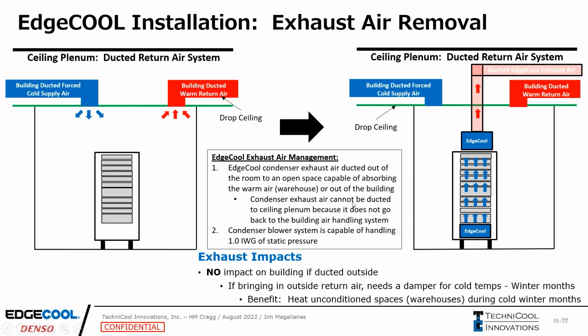The next would be a building ducted warm return system. So instead of just ducting the air up into the drop ceiling plenum, you have that cold air coming down only for business days. It doesn't operate nights or weekends. So we would put in an EdgeCool unit here, and we'd have to duct that warm air out to the outside of the building or to a warehouse that can absorb that warm air. Again, we can use that heat in unconditioned spaces like warehouses during the winter months, helping them out as well.